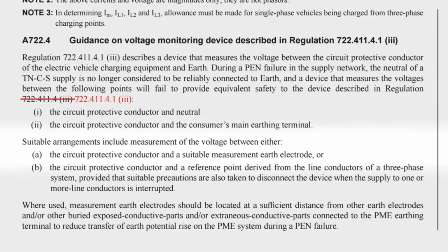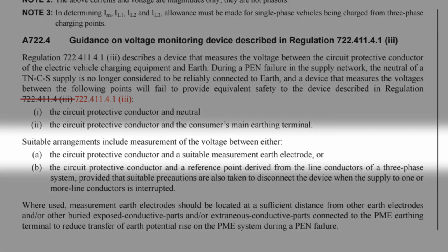It reads, suitable arrangements include measurement of the voltage between either A, the circuit protective conductor, and a suitable measurement earth electrode. So this method requires connecting to an earth electrode so the device can measure between the CPC and the earth, or what we can sort of think of as the hand and the foot. So if we're back to using an earth electrode, does that mean that we've just gone full circle and now we've got all the issues that come with driving an earth rod blindly into the ground?